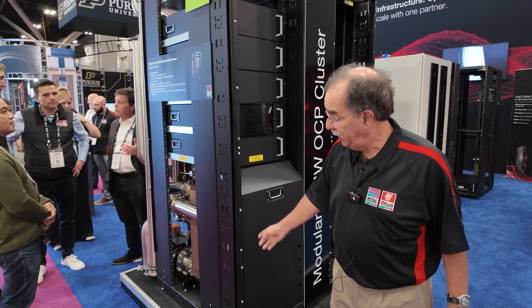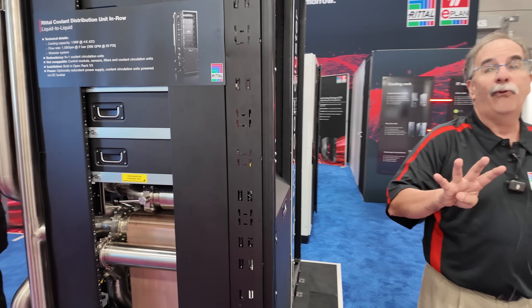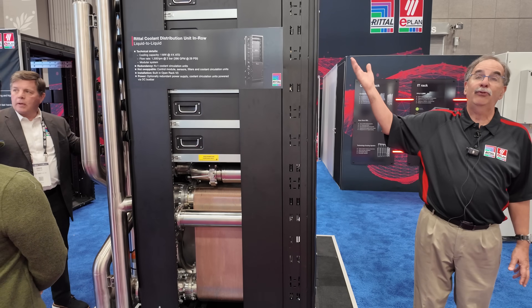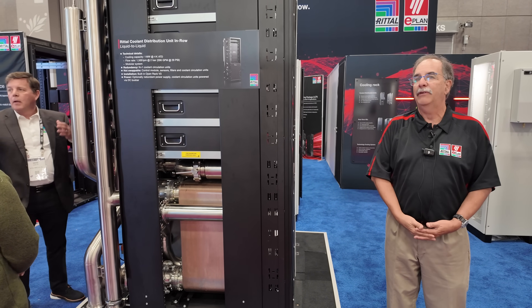So while we do have the one megawatt heat exchanger, we have individual drawers. Each tray or shelf is 250 kilowatts of heat removal capacity, just pumping. The heat exchanger — water to water — is down here. With five of these, we have four for the one megawatt heat removal, and then the fifth one, whichever it may be, is the N+1 for service in case something fails.